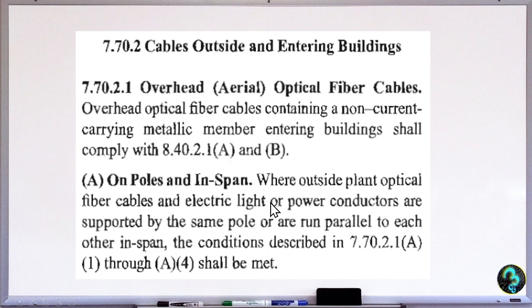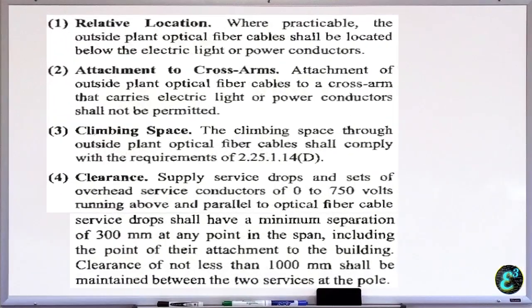So yung mga 300 mm na mga clearance, same po siya doon sa all communication na mga system, no? Okay, so for the relative location, where practicable, the outside plant optical fiber cable shall be located below the electric light or power conductors. Then the attachment of outside plant optical cables to a cross arm that carries electric light or power conductors shall not be permitted.